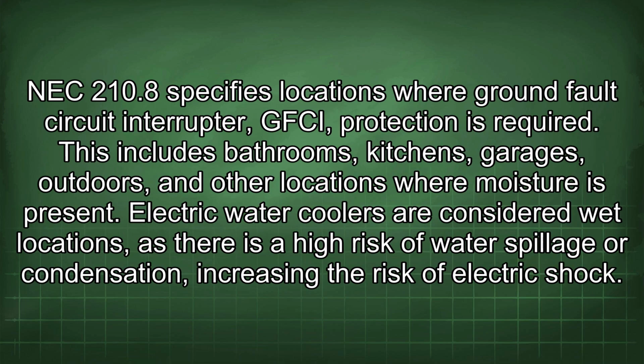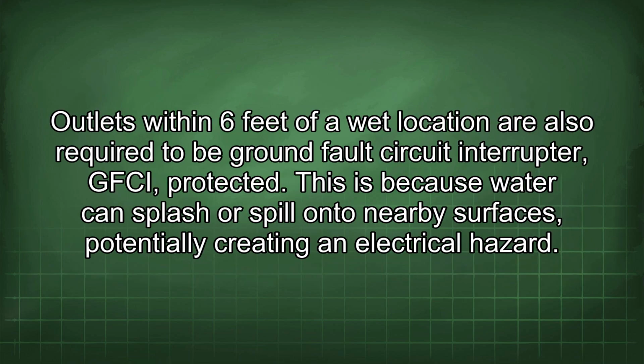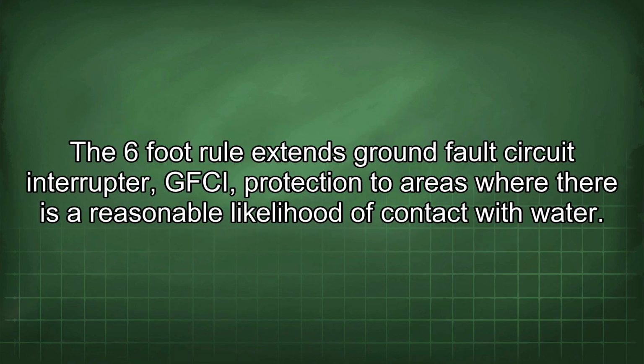NEC 210.8 specifies locations where GFCI protection is required. This includes bathrooms, kitchens, garages, outdoors, and other locations where moisture is present. Electric water coolers are considered wet locations, as there is a high risk of water spillage or condensation, increasing the risk of electric shock. Outlets within 6 feet of a wet location are also required to be GFCI protected. This is because water can splash or spill onto nearby surfaces, potentially creating an electrical hazard. The 6-foot rule extends GFCI protection to areas where there is a reasonable likelihood of contact with water.